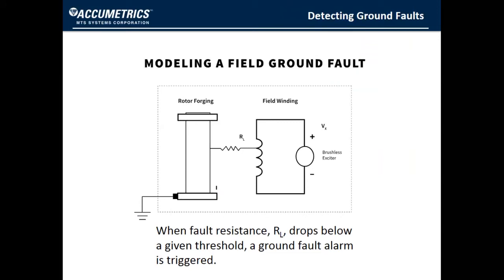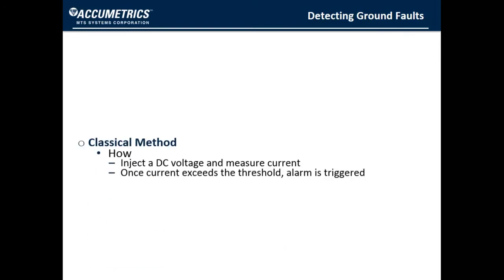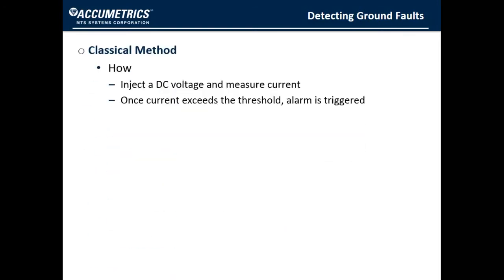So, once you have access to the rotor, how do you detect a ground fault? A ground fault can be modeled as a resistance between some location on the field winding and the rotor forging. First, we will look at the classical method that almost all ground fault detectors use. Typically, a detector makes a connection to the rotor forging and then to some location on the excitation circuit, in most cases the negative terminal.